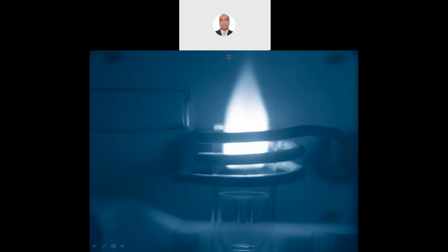plasma ionization state. In the plasma ionization state, there is the highest temperature when the sample comes from this injector in the quartz torch. This is the quartz torch, made from quartz to resist high temperature, and this is the injector for the sample to come into this area, make atomization, then make emission. The emission wavelength goes to the optical system to be measured by the detector. All these components, we will speak about in detail.